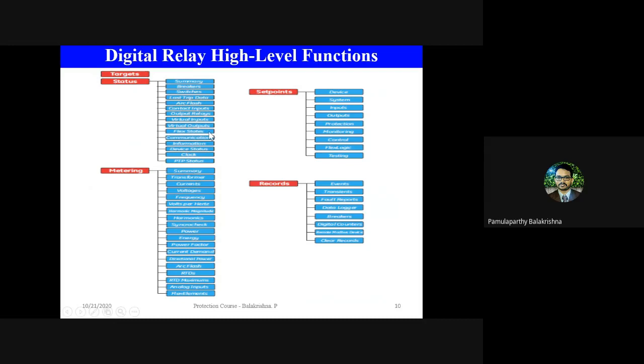Okay. Then the next major category is the set points, which are basically majorly protection-related set points. These set points are the flexibility given to the operators or the users in the field, where they can define how a particular protection function has to perform. So all relevant fields that need to be configured for a particular protection function to execute as per their need in the substation are configured as the set points.